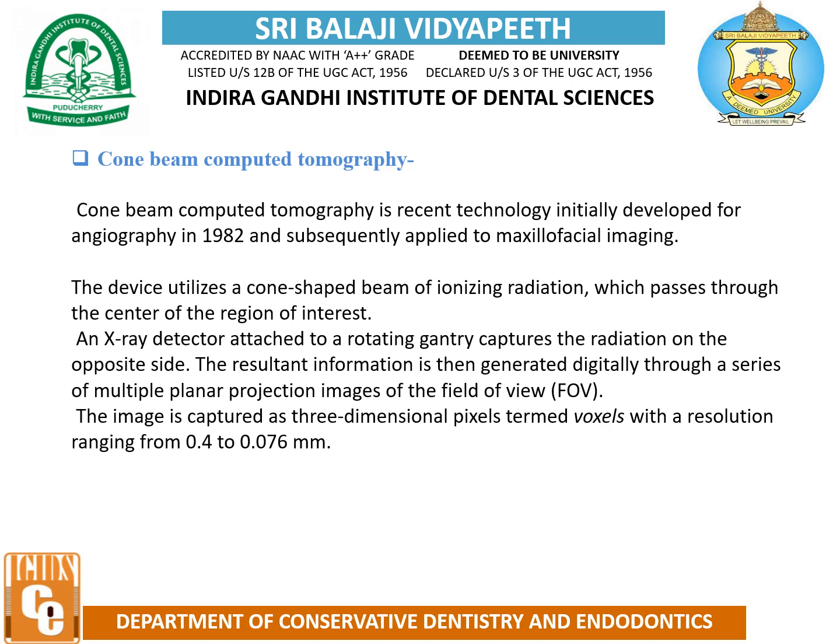An X-ray detector attached to a rotating gantry captures the radiation on the opposite side. The resultant information is then generated digitally through a series of multiple planar projection images of the field of view. The image is captured as three-dimensional pixels termed voxels, with a resolution ranging from 0.4 to 0.076 millimeter.